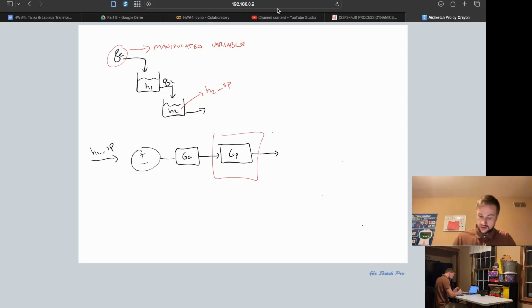So what we need to do is proceed by using first order plus time delay. And so dead time is a killer in systems, dead time being a lag. So you kick in your controller response, and it takes a few seconds or maybe whatever amount it takes. The system doesn't immediately respond. You shut off the hot water in your house. You can take a shower for probably a couple more seconds before the water becomes cold. So there's this delay, this dead time, and it really can be a killer to optimizing our systems and responding appropriately.